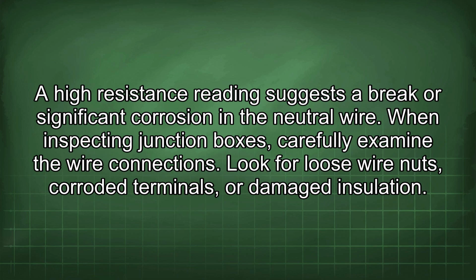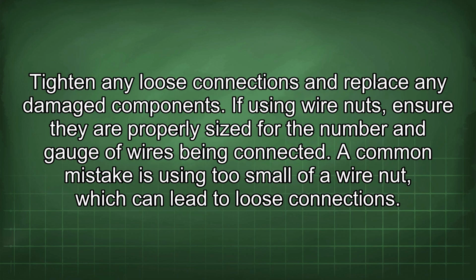When inspecting junction boxes, carefully examine the wire connections. Look for loose wire nuts, corroded terminals, or damaged insulation. Tighten any loose connections and replace any damaged components. If using wire nuts, ensure they are properly sized for the number and gauge of wires being connected. A common mistake is using too small of a wire nut, which can lead to loose connections.